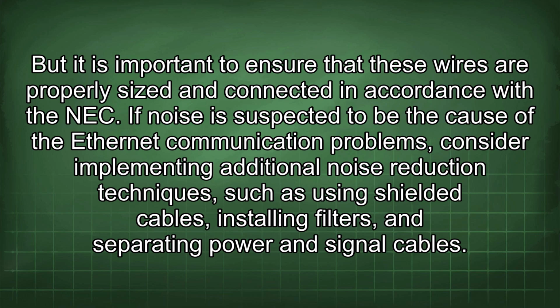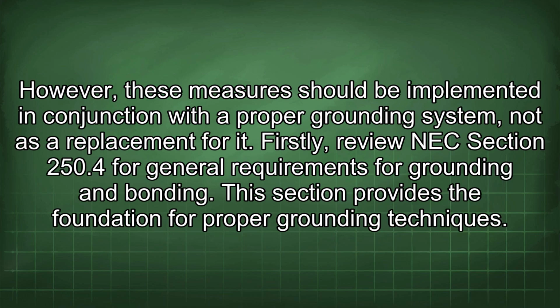If noise is suspected to be the cause of the Ethernet communication problems, consider implementing additional noise reduction techniques, such as using shielded cables, installing filters, and separating power and signal cables. However, these measures should be implemented in conjunction with a proper grounding system, not as a replacement for it.